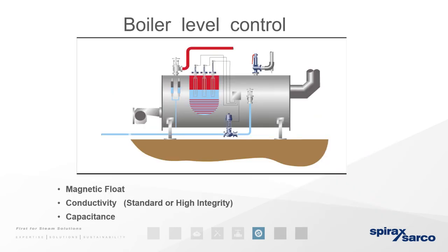Okay. So boiler level control, as you can see here, is slowly running through where it's got the steam. So we need a high, first low and a second low alarm, and then also a level control probe mounted in at least 2 chambers. So as we were saying before, you've got 2 separate alarms there, and that's so that they're independent. So if one fails, the second one shouldn't, and that gives you added protection on your boiler. There are a number of different level control types. Most popular being used are steam boiler, mag float, conductivity, capacitance. Those tend to be the standard ones in the market.